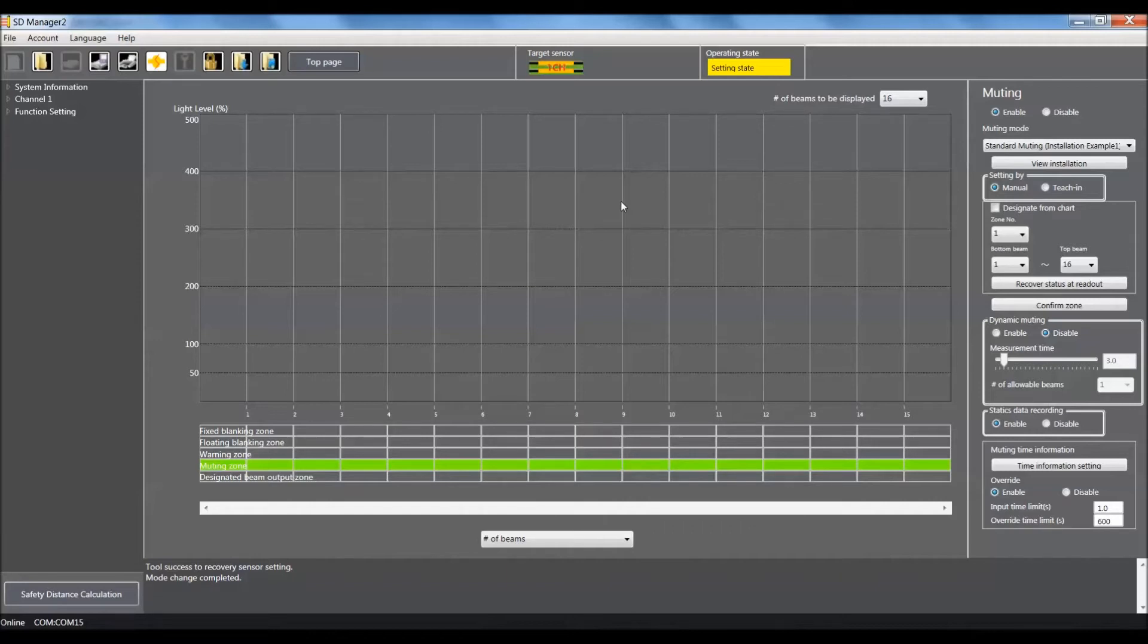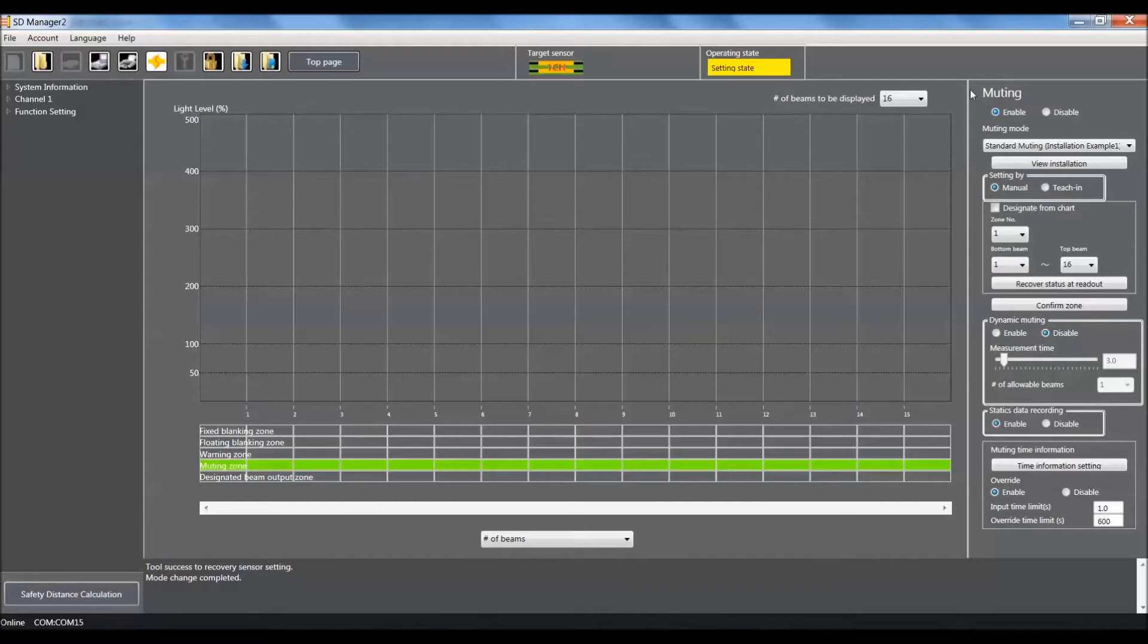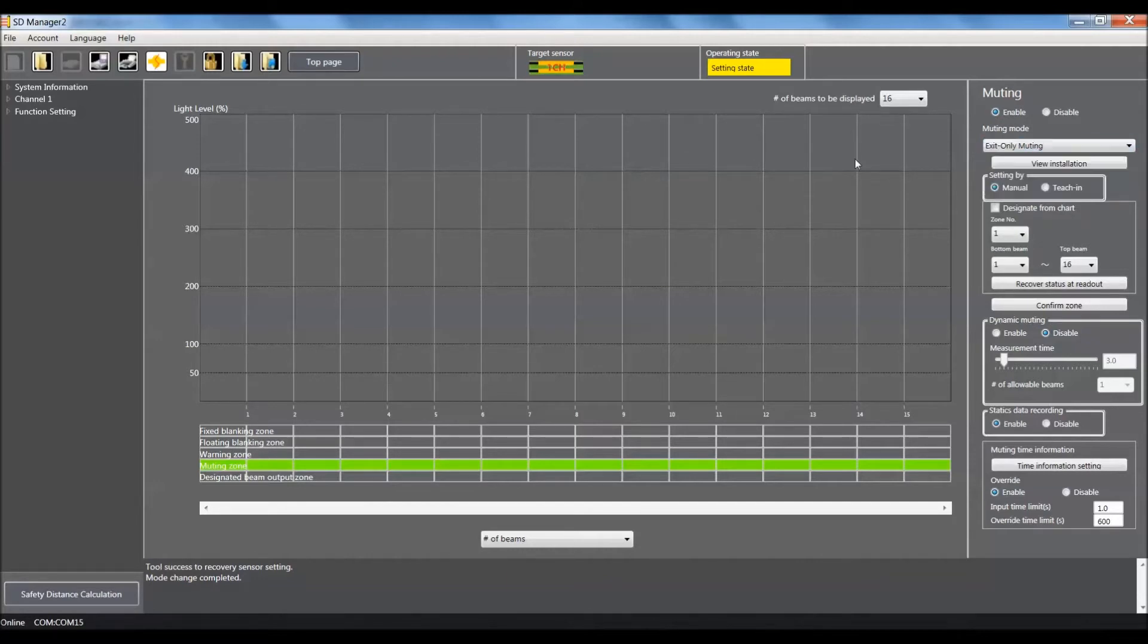Since I do have my object in the beam presently, I'm going to use the teach-in function. Before, on other videos, we showed how to manually set this up, but this time I'm going to show the teach-in. Since we're using the F3W muting sensors, we need to make sure muting is enabled, then use this pull-down and select exit only muting.